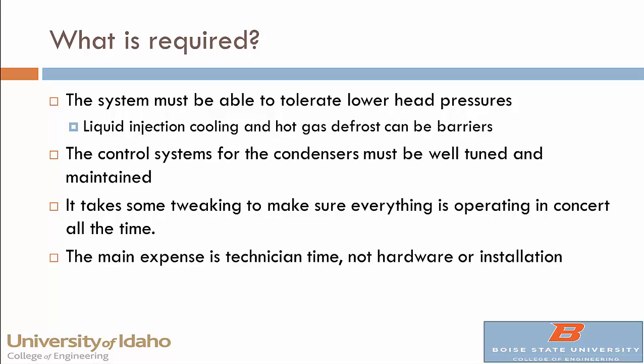And that's because these systems can be a little finicky, and there's other things that can go wrong if you're not careful. So we talked about cooling. They sometimes do liquid injection cooling for the compressors. We talked about hot gas defrost. These are all things that you need to check into and talk to the operators about. And basically, it's something you've got to keep on top of. You've got to make sure it's still working. It takes time. So the main expense is technician time. They probably need to bring in an outside technician for a day to make sure it's working right. So that could be a couple thousand dollars easy.